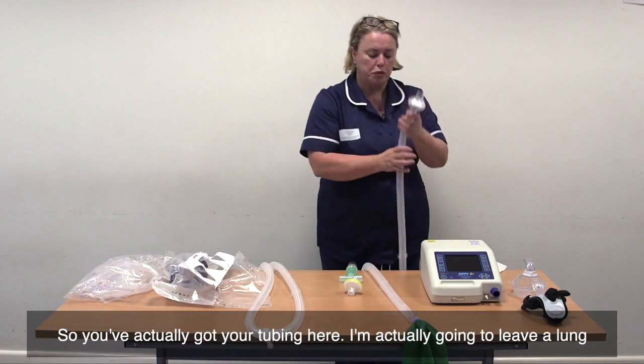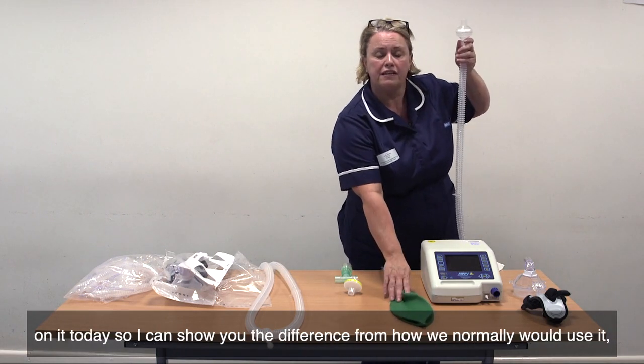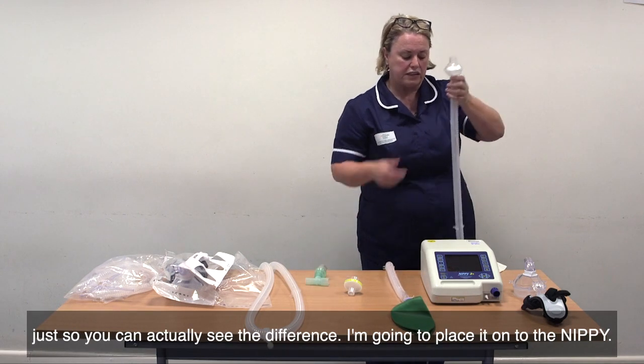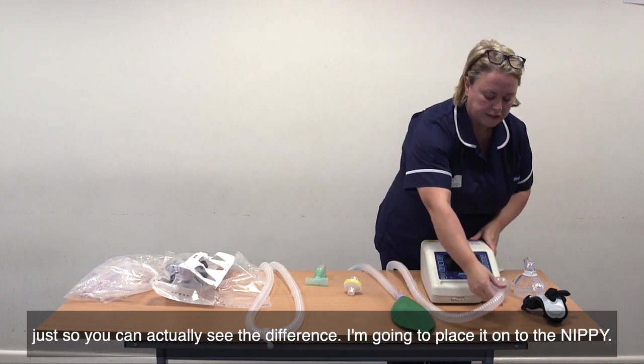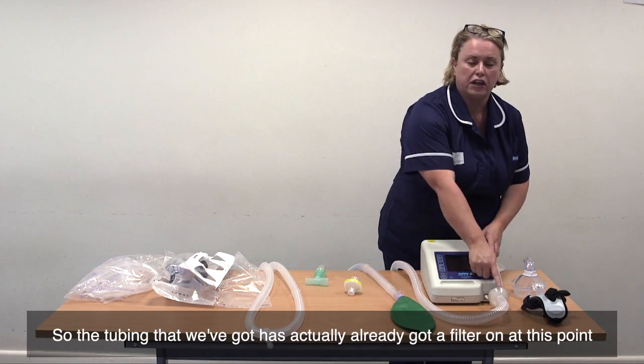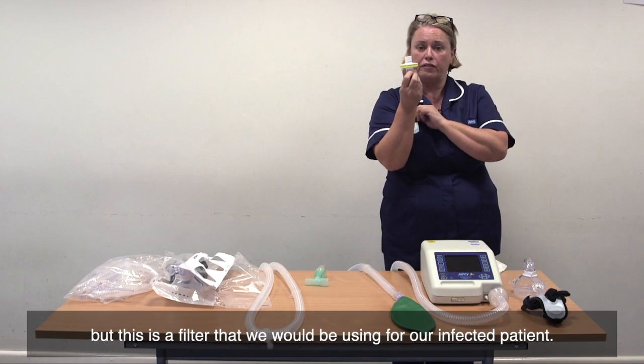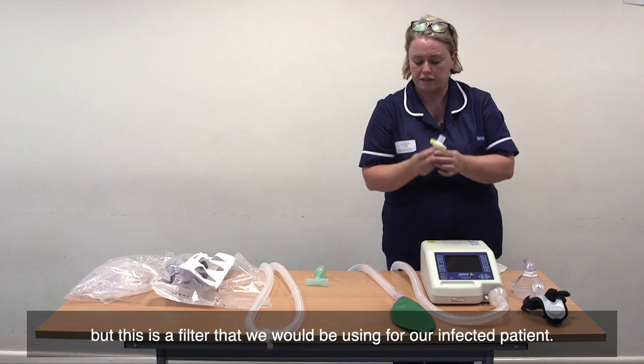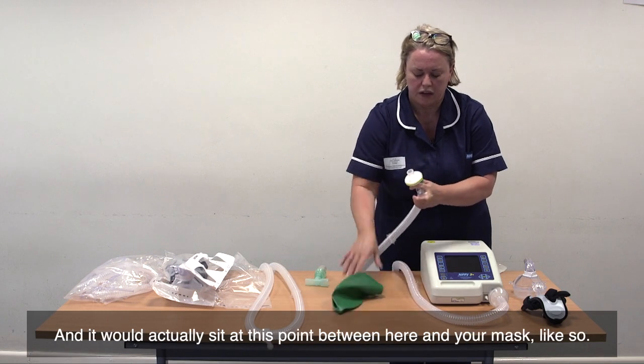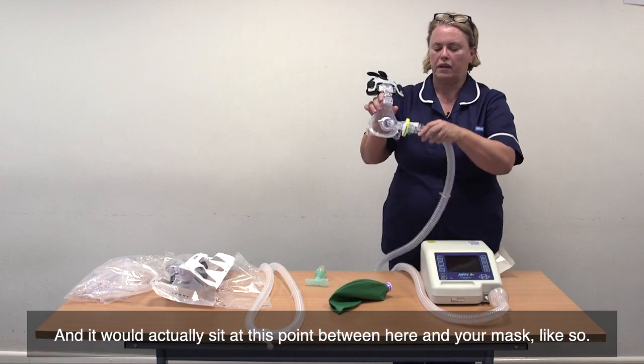So you've got your tubing here. I'm going to leave a lung on it today so I can show you the difference for how we normally would use it. I'm going to place it on to the NIPPY. The tubing has already got a filter on at this point, but this is a filter that we would be using for our infected patient. It would actually sit between here and your mask, like so.